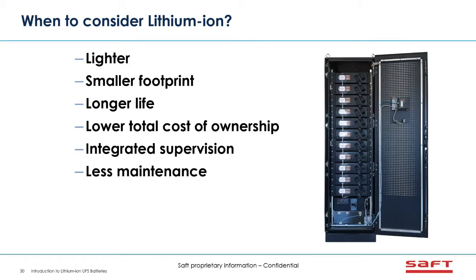To summarize, when to consider lithium-ion, it's a lighter technology versus lead-acid battery. You're talking 10 to 20% of the weight savings, smaller footprint, roughly half, much longer life, lower total cost of ownership. It has the integrated supervision, and it requires less maintenance. And here, typically, we see lead-acid batteries requiring annual discharge tests. And for our system, it's really roughly 2 seconds per string to do the maintenance. We have a built-in auto test that typically just checks the internal contactors. It takes about 2 seconds per string to run through that test.